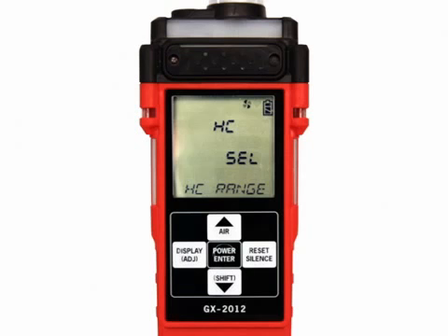If percent volume is selected, the combustible gas reading will be displayed in percent volume only. If the combustible channel is set for percent volume only, then there are no gas alarms for any detection channel, and no alarm will appear in the upper left corner of the screen. To update the HC range setting, after entering display mode and arriving at the HC range screen, press and release the Power Enter button. The current setting will appear at the bottom of the LCD.